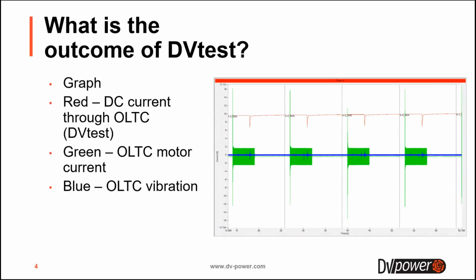So what we actually get with the DVtest is a graph, and you can see here on this photo an example of a DVtest graph. The red graph represents the DC current which is injected through the on-load tap changer, and we also call this part a DVtest graph. The green one is the on-load tap changer motor current, which is also recorded, and the blue one is the vibration of the on-load tap changer. So you get a graph with up to three parameters. The most important of them is this red one, the DC current through the on-load tap changer, and we will mostly focus on that one in this presentation. But the other two, the OLTC motor current and vibrations, can also be very useful for detecting possible issues and problems in the on-load tap changer.